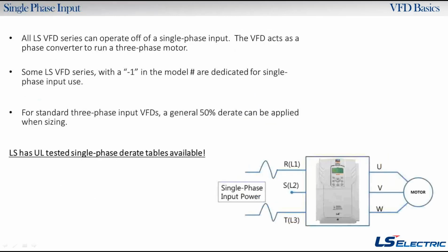All right, here's something about single phase inputs. This is the next common question we get about VFDs, and it's very important when you're selecting a VFD. I always ask, are you running single phase power or 3-phase power? If you don't know, you better find out, because that changes a lot. All of our VFDs are able to operate off of a single phase input. When I say single phase input, you just have a line 1 and a line 3. You're not using line 2. So you're only using part of the input diode bridge on the front end, and you're not fully doing 6-pulse 3-phase rectification. We also have drives that are rated for a single phase input -1, and there's no derate required.